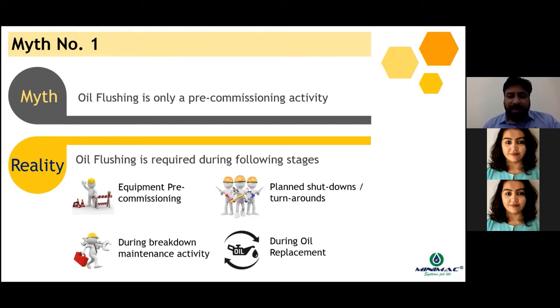But as a matter of fact, flushing is highly required, not just during your pre-commissioning, but also during your plant shutdowns and turnarounds. It's required during the breakdown maintenance activities, after you have completed your repair work and you have recommissioned your equipment. At that moment, you will require flushing. And it's also required when you replace your oil in terms of grade changes or in terms of oil manufacturer changes. So there are 4 different activities when oil flushing might be required by your plant.